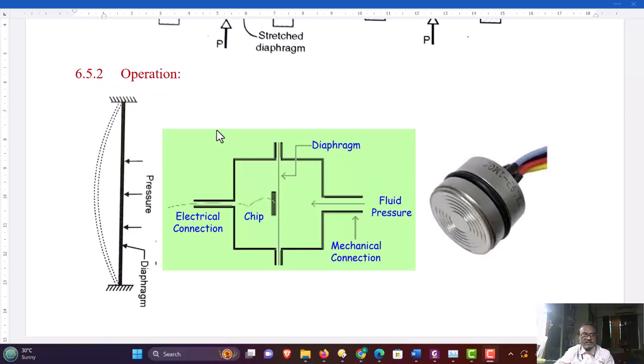Typically in a sensor using the diaphragm as a primary sensor, as shown in the figure here, see, this is a diaphragm. There is a fluid port available from which the fluid enters the chamber. The mechanical connection is provided for that purpose. This fluid exerts the pressure on the diaphragm. On the other side of the diaphragm, there is a sensor which measures the displacement of the diaphragm.